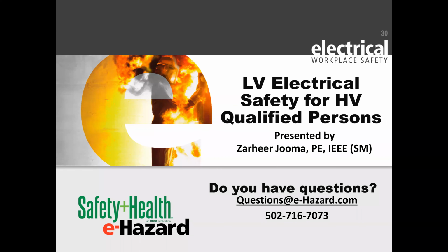Does the OSHA definition for energized, de-energized, and previously energized for high voltage apply to low voltage? Ooh, interestingly, I'm not 100% sure I understand this question. The definition for energized at high voltage is anything that has not been grounded. At low voltage, you can have a system that's de-energized without it being grounded. So I'm going to say the definition of energized per HV will not apply to energized for LV.